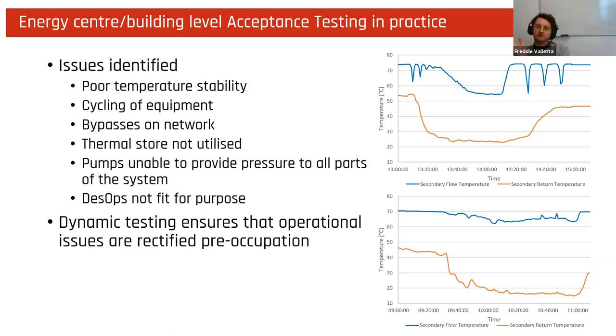Once these issues were investigated and the changes were made, the fluctuation was completely eradicated on a reiteration of the load test, and the secondary flow temperature didn't drop nearly as much as the first time. This was then rectified further on the day to ensure that this secondary flow temperature remained stable and the risk of heat delivery at elevated demand was drastically reduced. This dynamic and iterative testing ensured that these operational issues were rectified pre-occupation. So I'll hand back over to Ellen, who will then go through acceptance testing from a dwelling side.